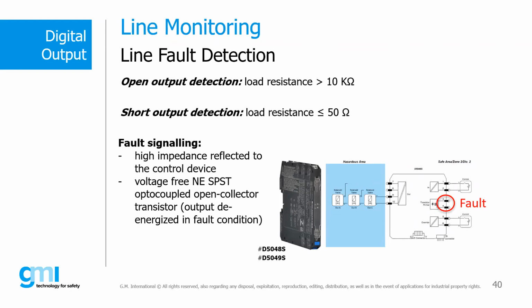The other model, the D5049S, on the other hand, being bus powered, provides a complete diagnostic towards the field, both in condition of load on and in condition of load off. Like the D5048S, it can transfer the fault information directly to the digital output card of the PLC with an impedance variation, or through a voltage free contact to be acquired with the digital input card of a DCS dedicated to the purpose.